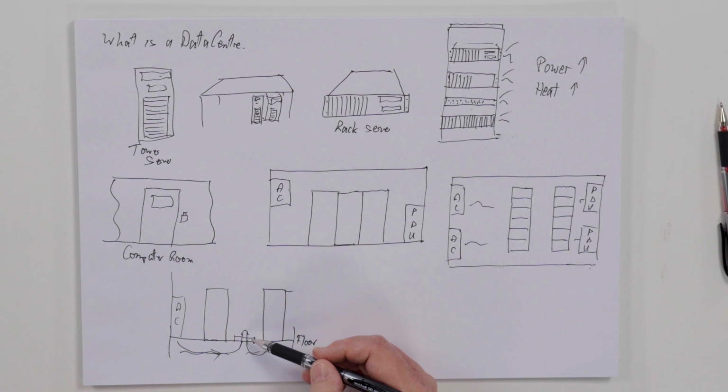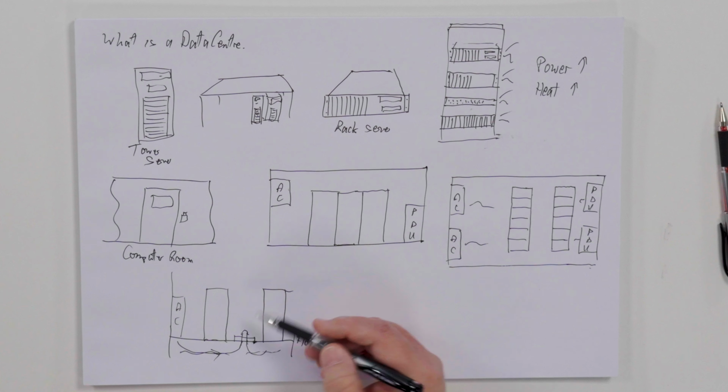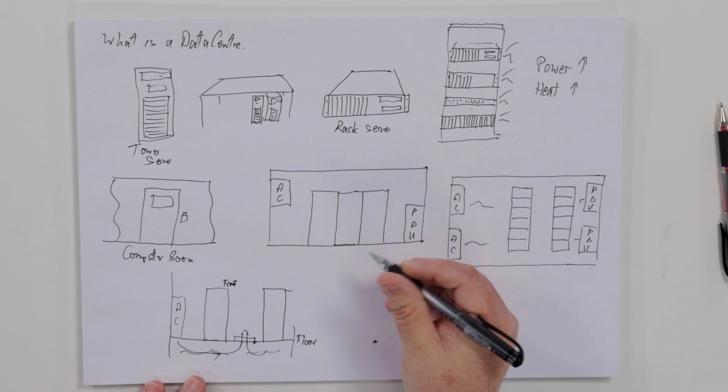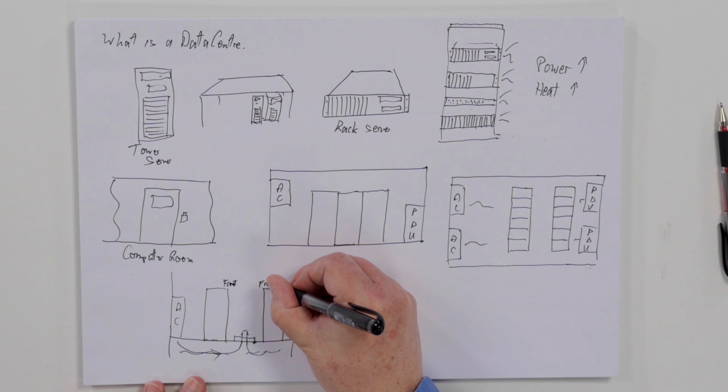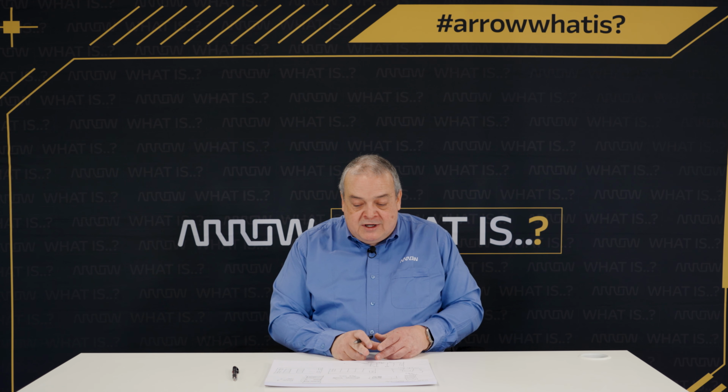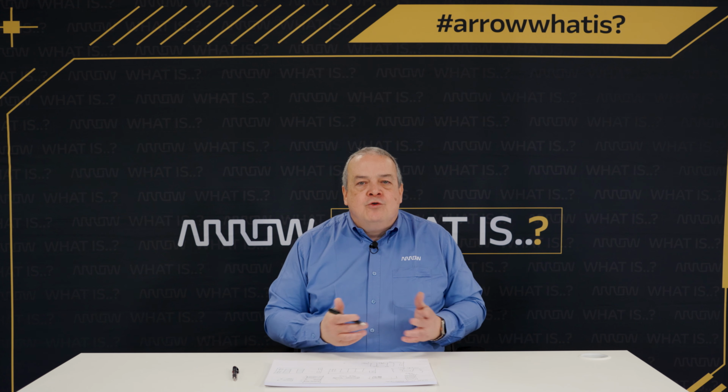So we have a cold aisle in the middle of our 2 rows of racks. So we have the front of the equipment and then the front of the equipment facing each other. So basically when we put the technology together, the servers, the storage, the networking, the air flow inside the servers to maintain an optimal cooling for the device is from the front of the device through fans and then out of the rear of the device.